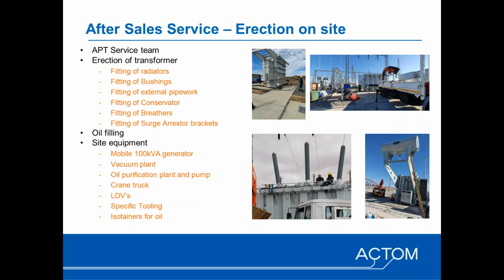When the transformer arrives on site, it has to be put together, and sometimes customers find this is something they can save money on. We find this is a very critical area in the transformer's life, because if it's not put together properly, or the conditions under which it is assembled are not ideal, the transformer suffers at the beginning of its life in service.